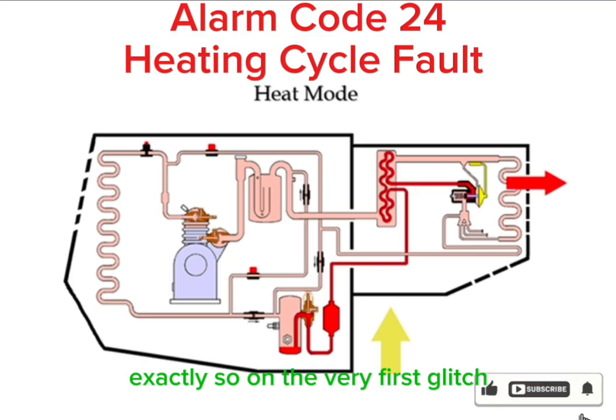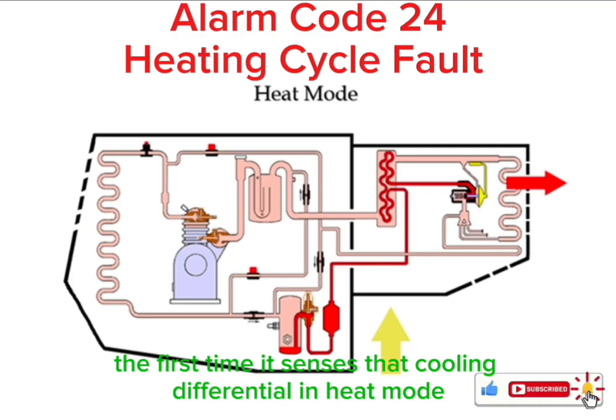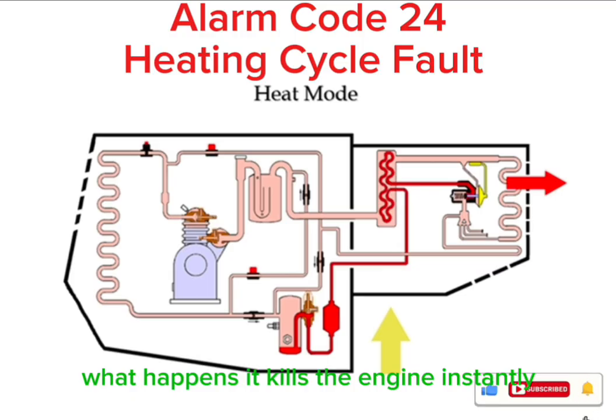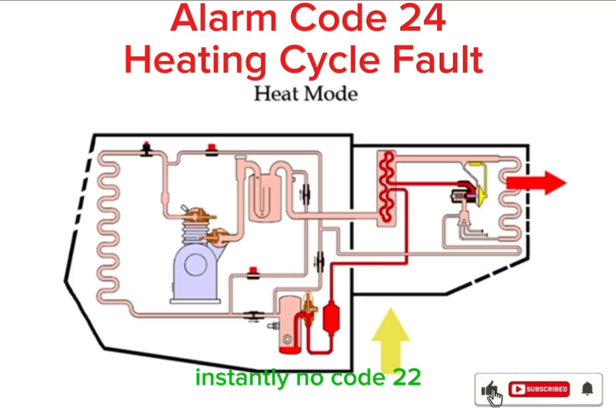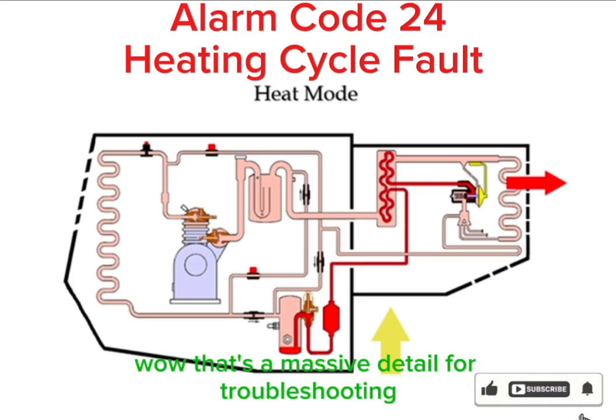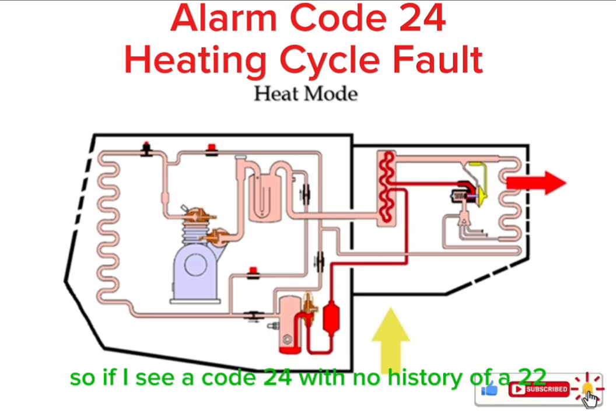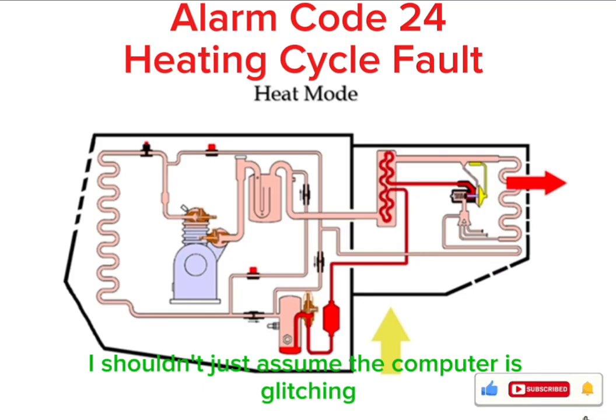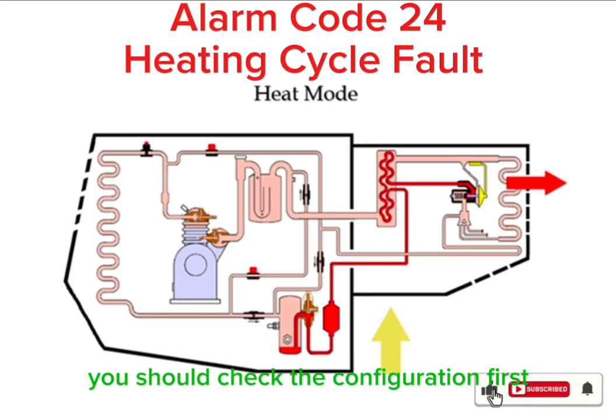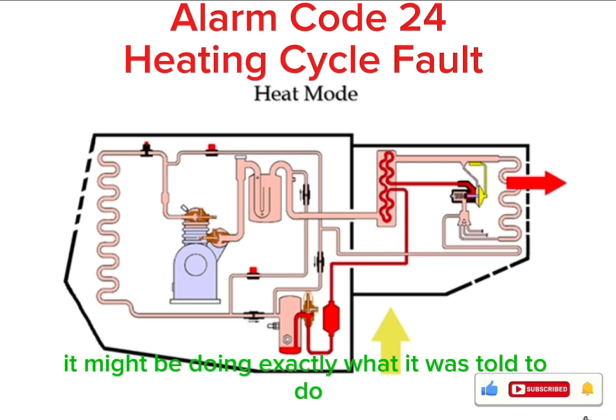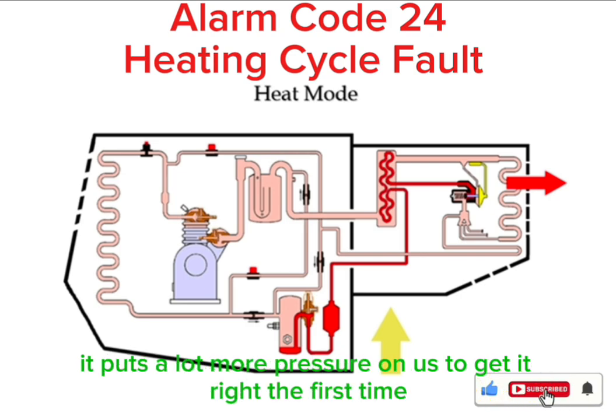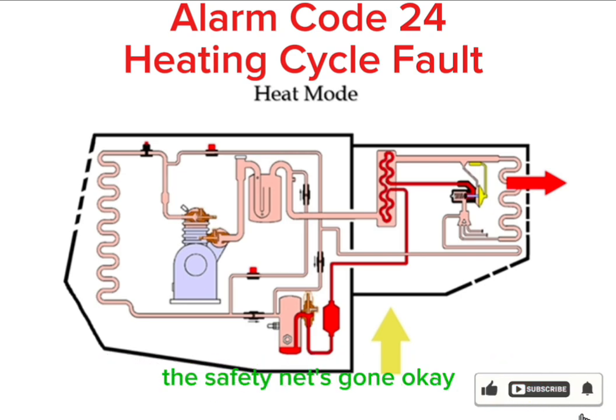Exactly. So on the very first glitch, the first time it senses that cooling differential in heat mode, what happens? It kills the engine. Instantly. Instantly. No code 22, no second chance. It's a hard stop. Wow. That's a massive detail for troubleshooting. So if I see a code 24 with no history of a 22, I shouldn't just assume the computer is glitching. You should check the configuration first. It might be doing exactly what it was told to do. It puts a lot more pressure on us to get it right the first time. The safety net's gone.